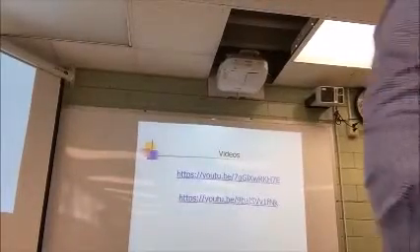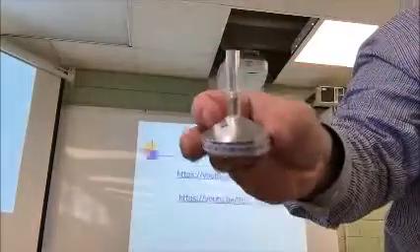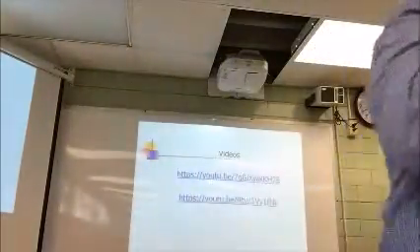So just so you guys know, again, the calibrator, I'm going to pass that around, and actually the PPI with the filter preloaded. So it goes together like that. And I'm going to send that around, and when you do calibrate it, obviously your pump's there, and you pull through it. And you notice you've even got those set up. So there you go, guys.